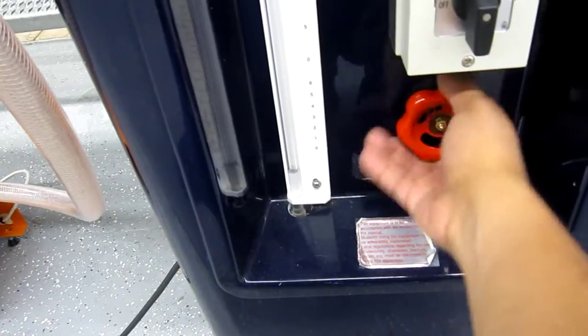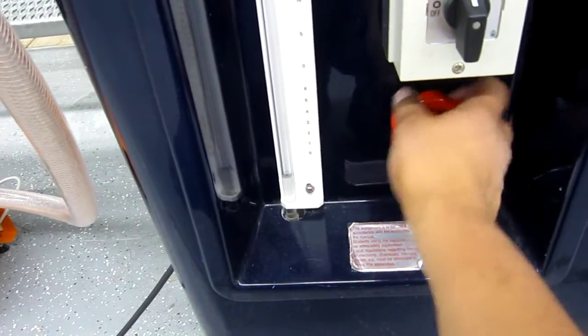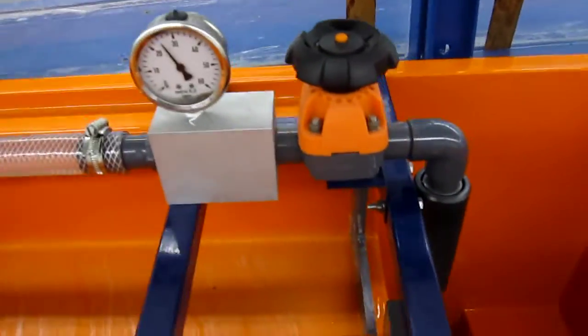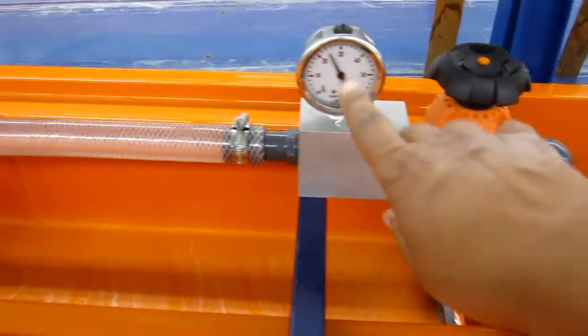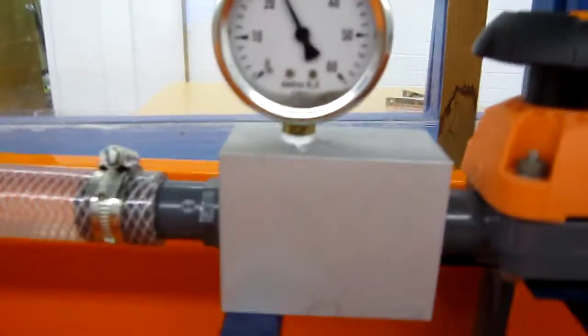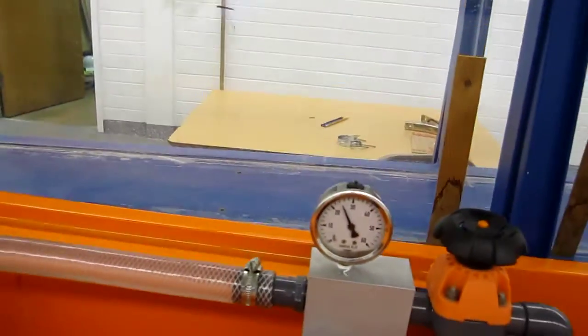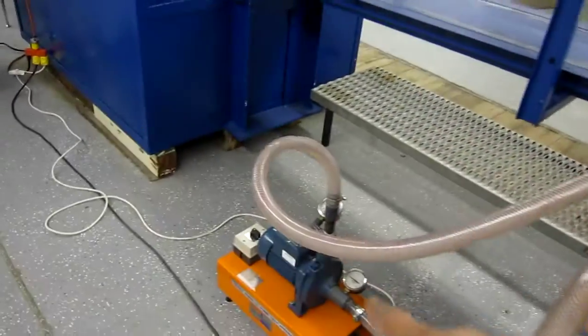We're going to control the discharge by using the system valve there, the manifold valve up here. Now right now we have one pump operating. The system head is about 25 meters of water. This is what we did last time using the single pump right here.